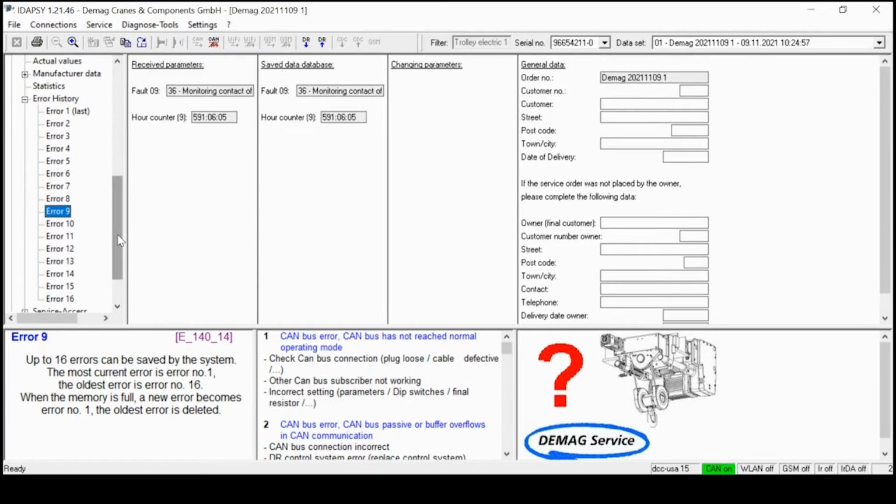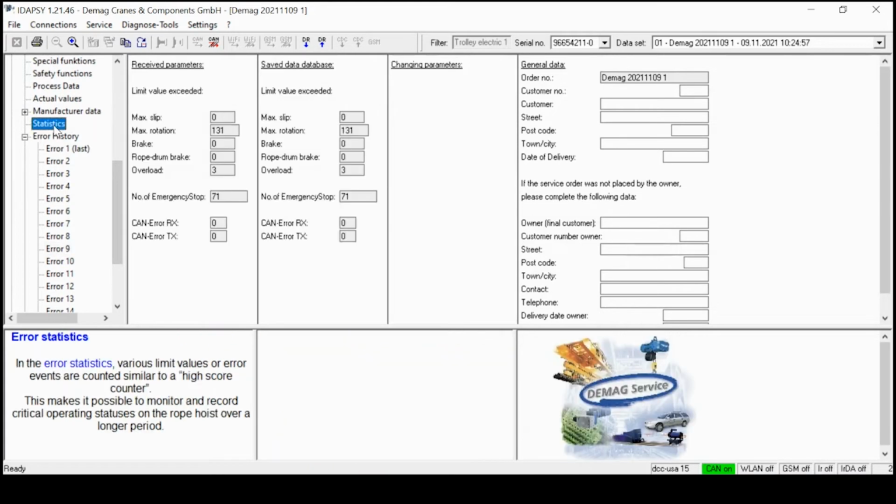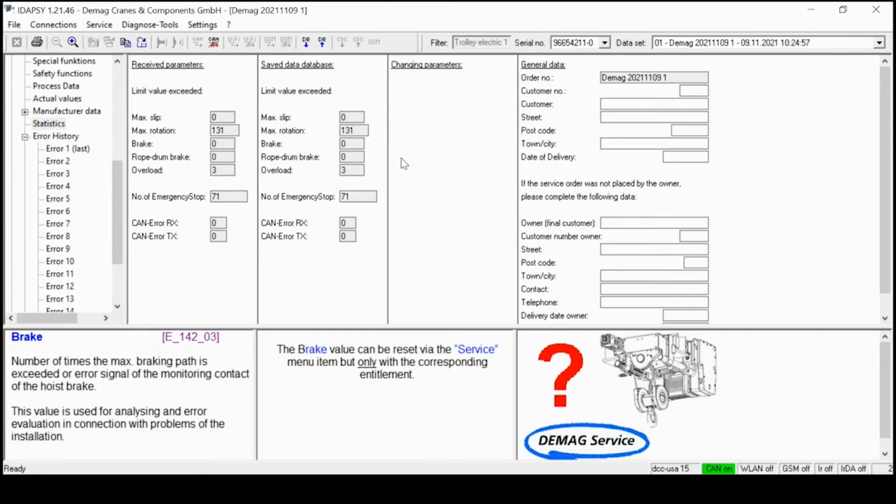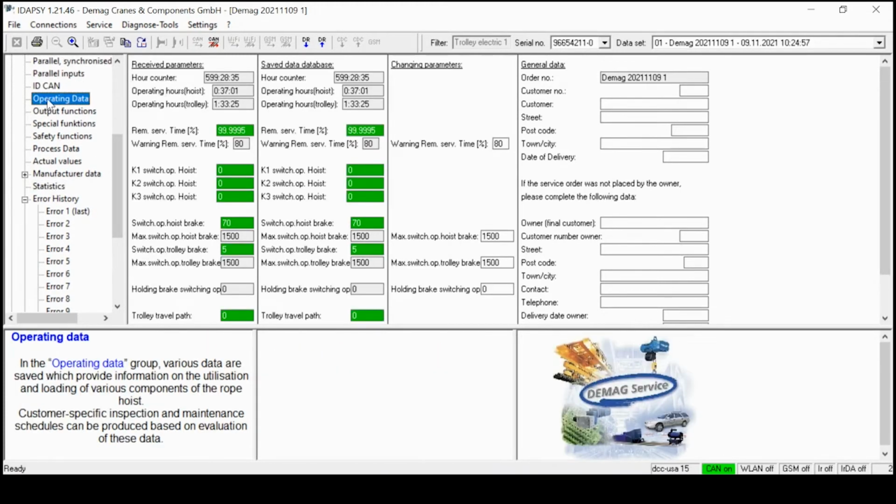The other folder that's important to look at is statistics. Statistics actually tracks recorded overloads that happened to the system. It also records how many times the brake has allowed over-travel beyond limits. So if the brake adjustment were ignored on the hoist, eventually you will trigger a statistic of 1 in this box, and it will trigger the wrench symbol, and it will only operate the hoist in low speed when that happens.